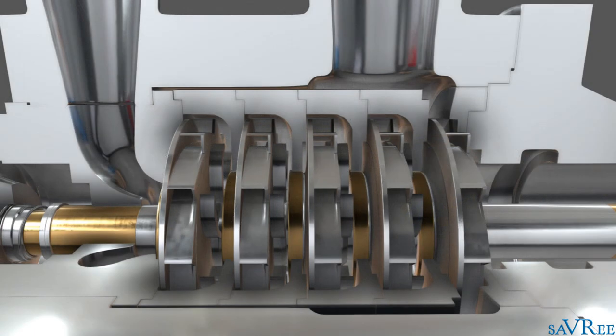Each impeller and diffuser are classified as one stage. Our pump has five impellers and five diffusers. Therefore, it is classified as a five-stage pump. It's important to realize that at each stage, we're increasing the pressure, but there is no change in the flow rate.